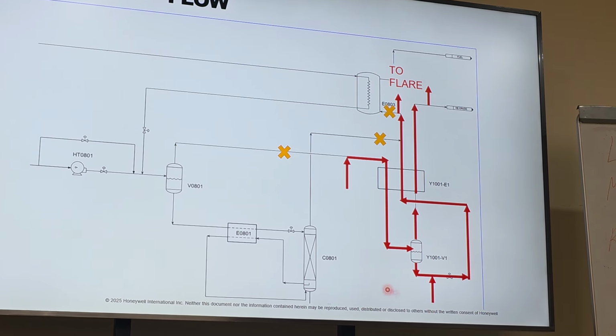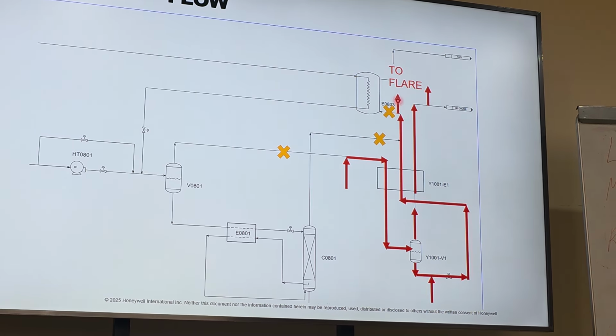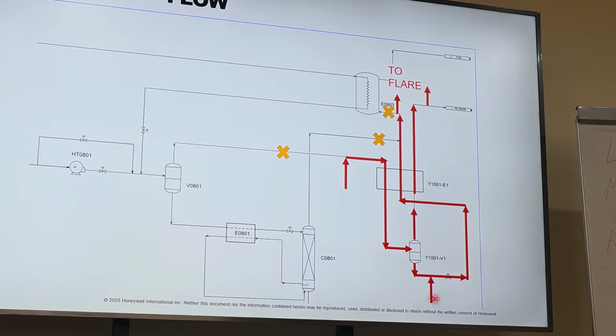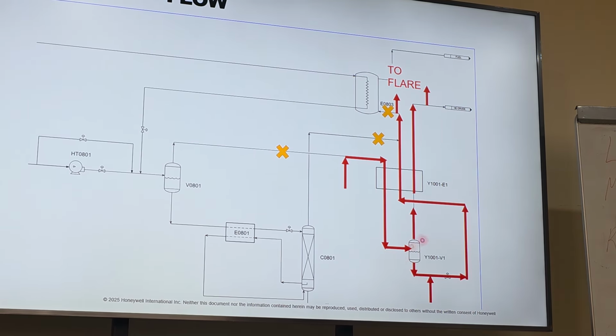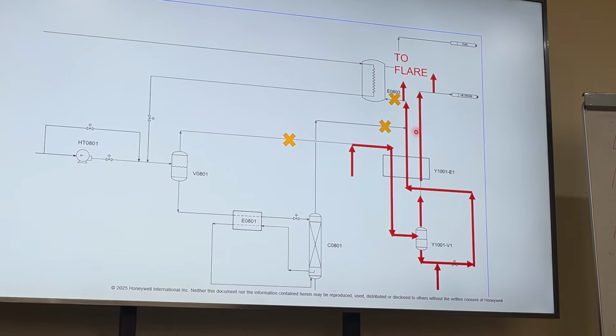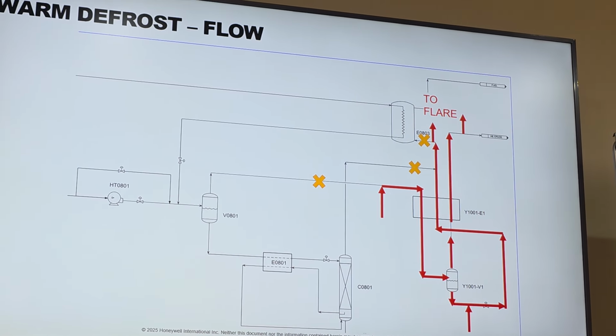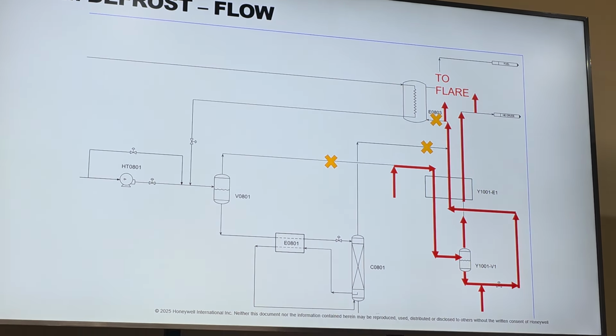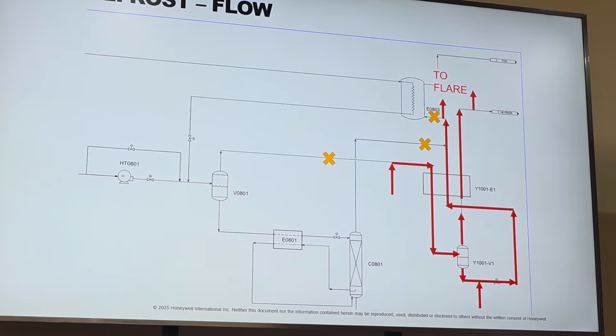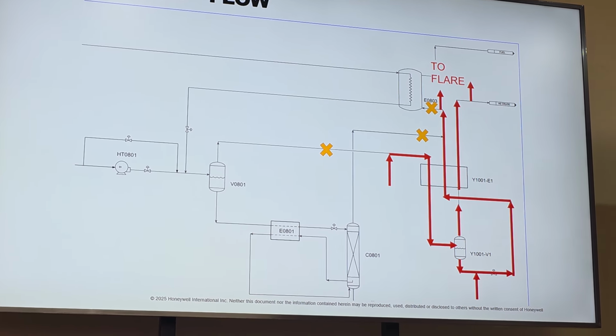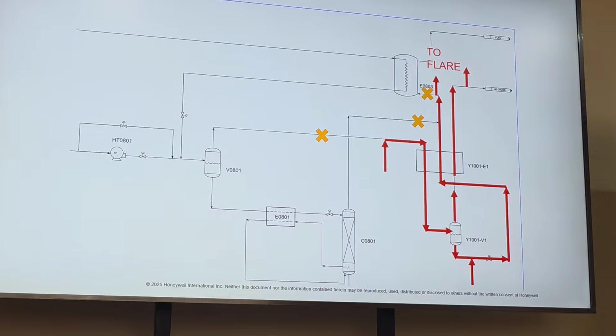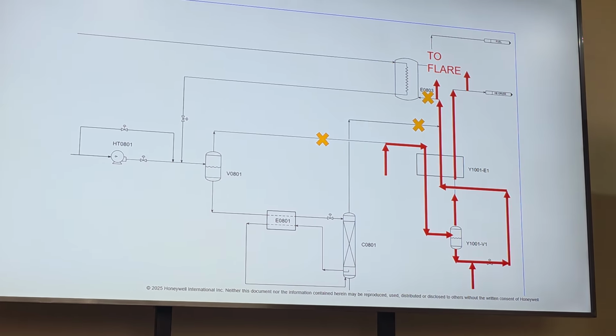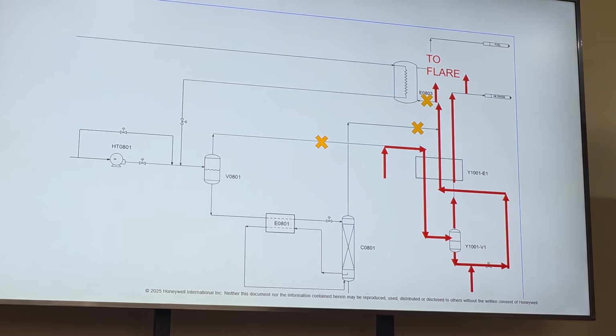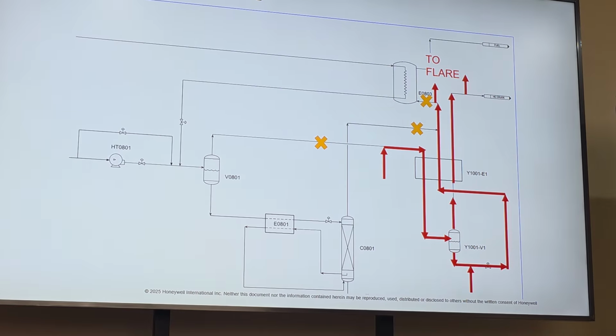So you can see, I'm highlighting once again multiple vent points, multiple defrost gas injection points. You can open up drains on the flash drum. You can open up drains throughout the process piping, okay? The nice part about Unit 10, it can be done separately. You don't have to actually mix it. So, any questions about a warm defrost? The same rules apply. We want to get to 55 degrees C, less than 10 ppm of moisture coming out.